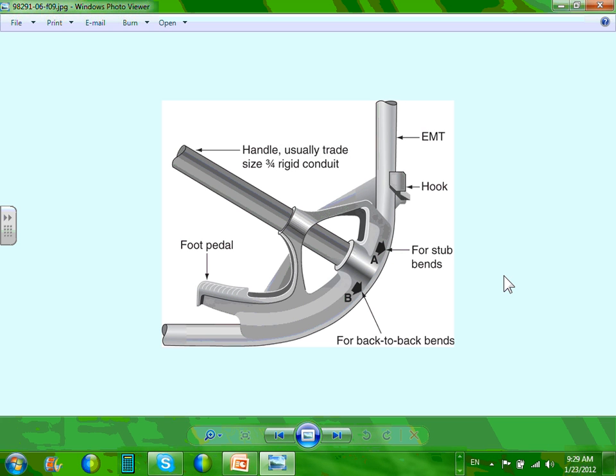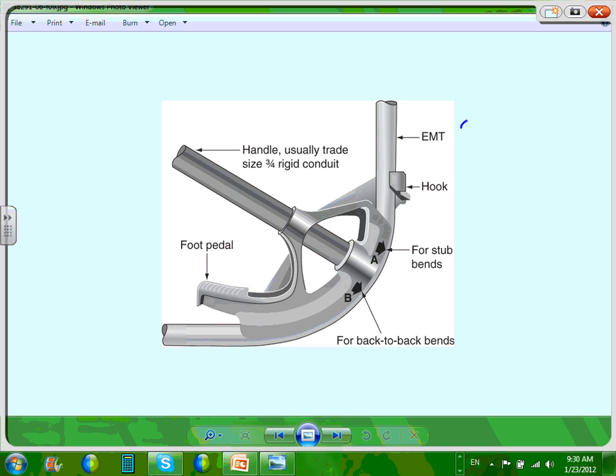Okay, bending. You guys are not electricians, but you should be able to understand that if you're using EMT, they have to do some bending. You've seen EMT conduits that you can bend. We have one in the lab right now that we can bend, up to 2 inches. EMT, you can bend up to 2 inches.